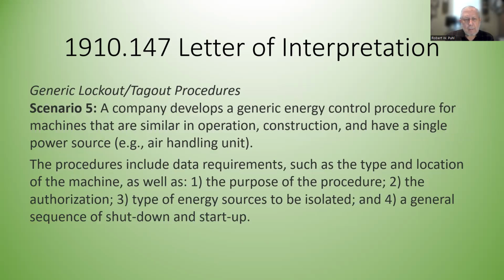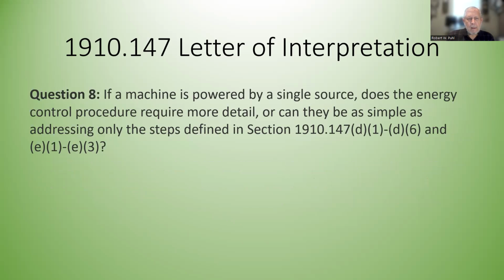Scenario 5. A company develops a generic energy control procedure for machines that are similar in operation and construction and have a single power source, an air handling unit, for example. The procedures include data requirements such as the type and location of the machine, as well as the purpose of the procedure, the authorization, type of energy source to be isolated, and a general sequence of shutdown and startup. Question 8: if a machine is powered by a single source, does the energy control procedure require more detail, or can it be as simple as addressing only the steps defined in the section, which I'm not going to read?